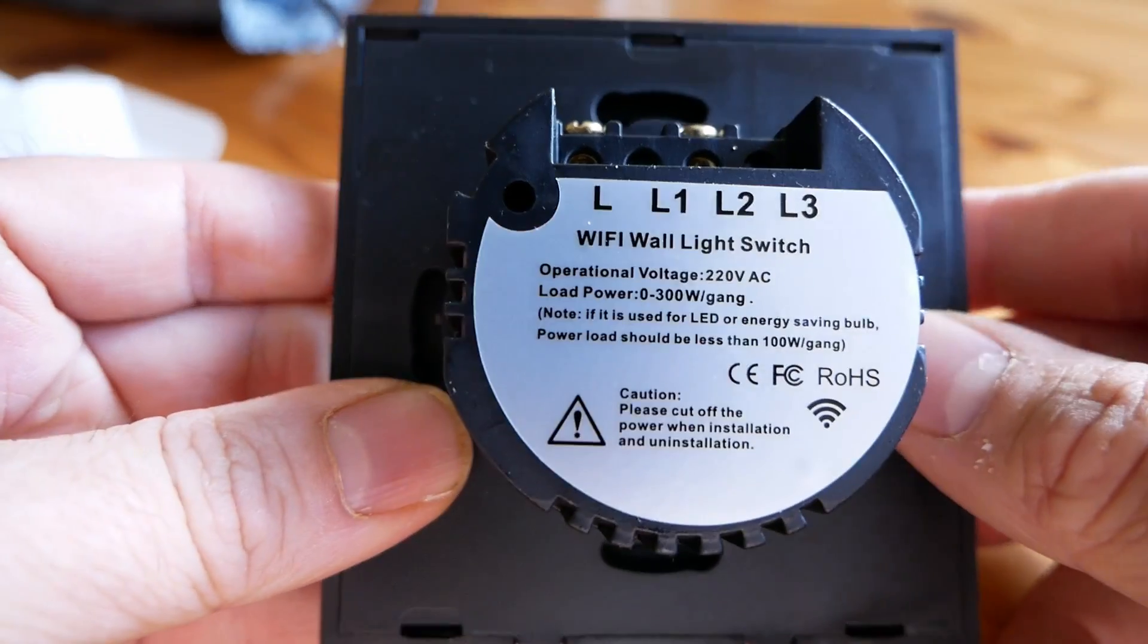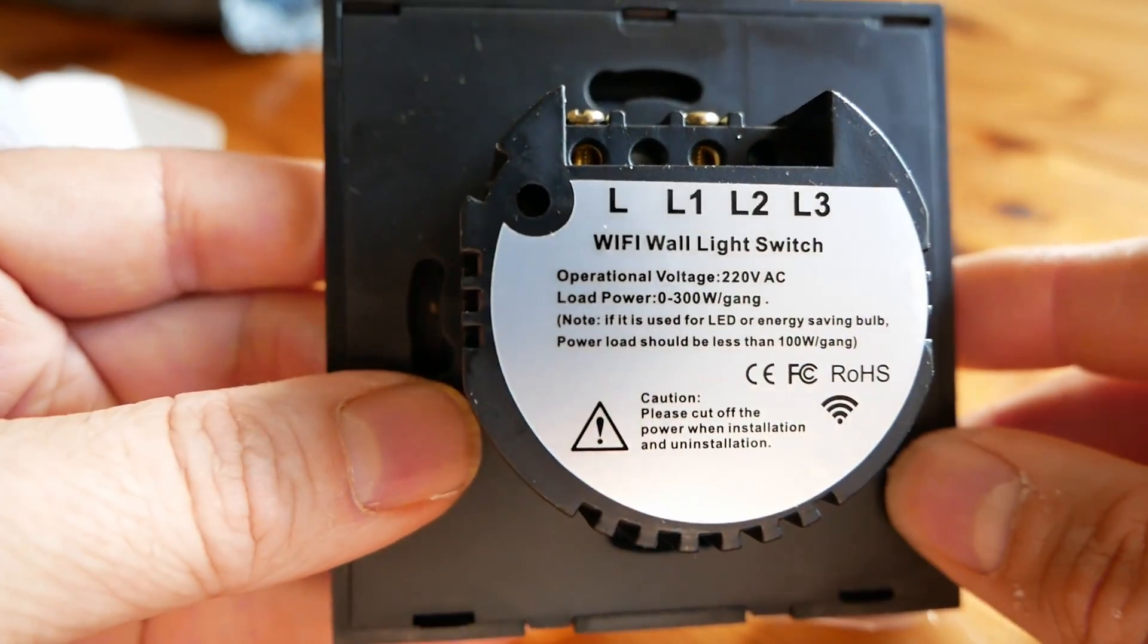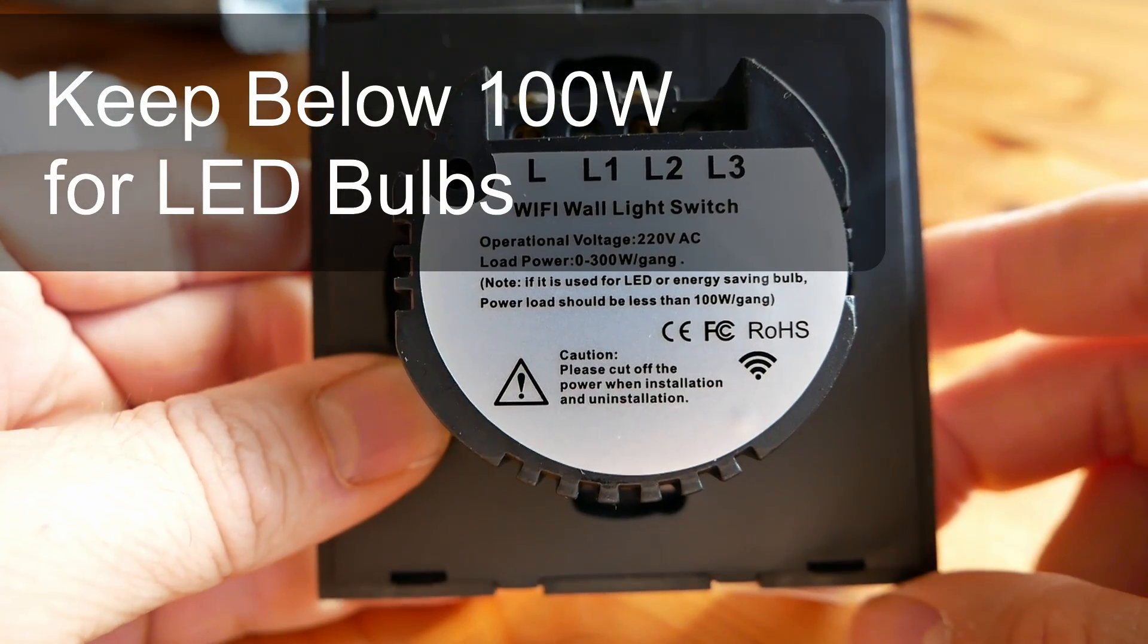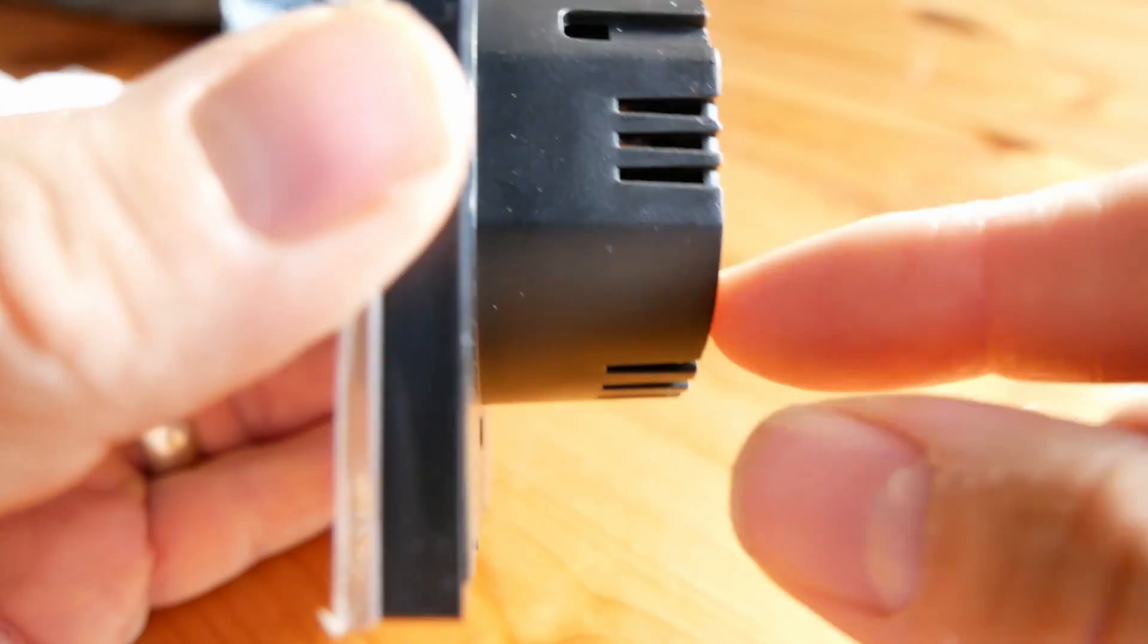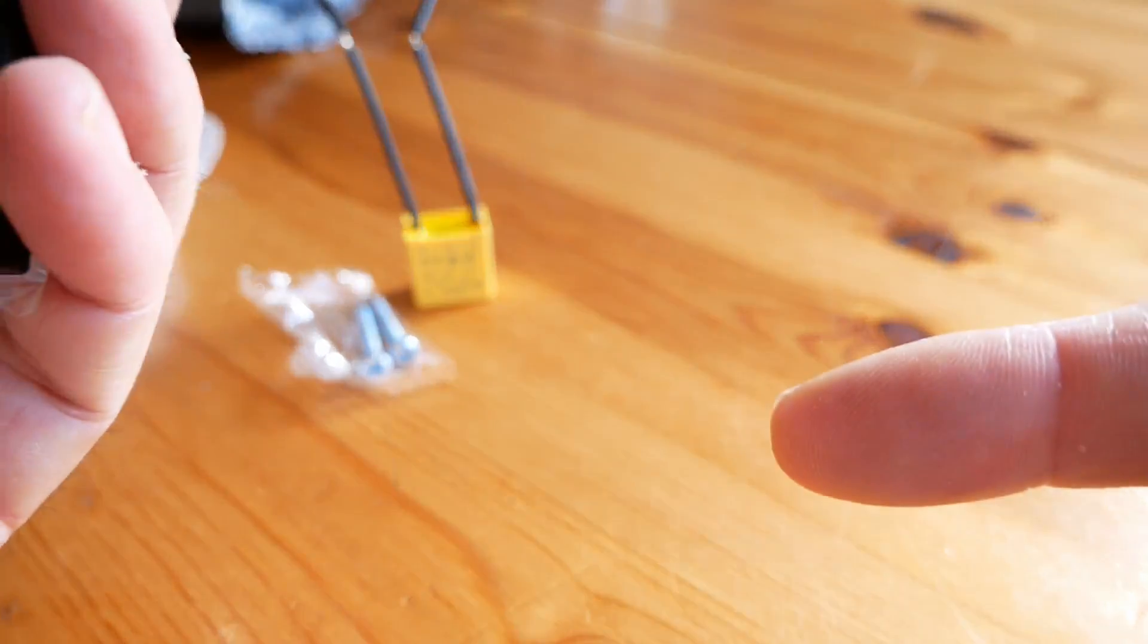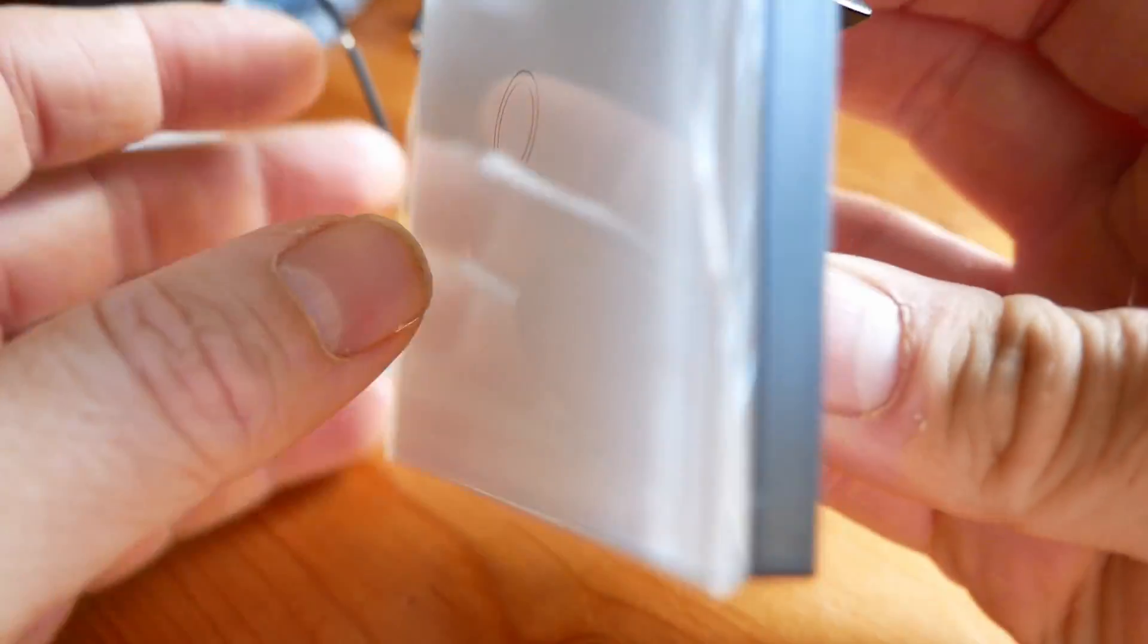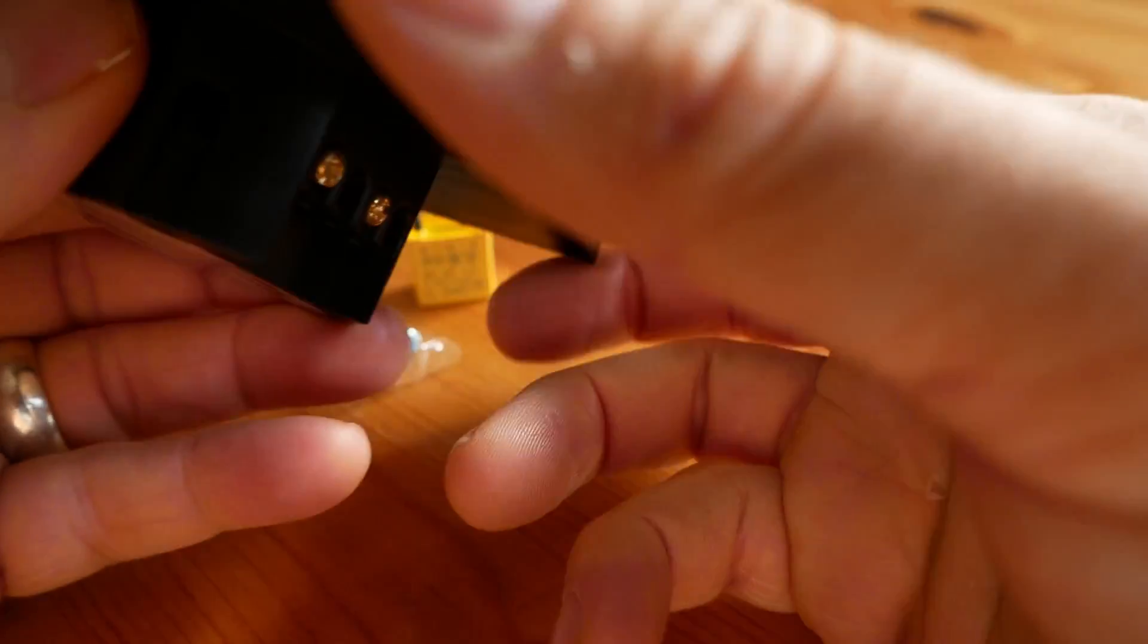So one of these switches can run 300 watts. So you just need to be careful how many lights you've got on. 300 should be plenty for most people's lights. Obviously check your power requirements. Also check how deep your backing box is and make sure that that's going to fit in. This sits on the surface of your wall. So what's on display is this cross section here. And that's the glass front. So it looks quite nice.